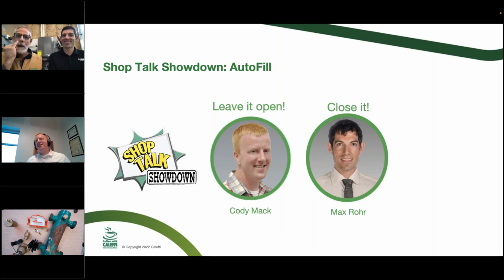No. See, so here's another thing to think about. Okay, say you close off that valve. Okay, you have a leak somewhere and you're not home. It's going to leak out a little bit. It's going to be all done, but then all of a sudden that pressure sensor in the boiler or the low water cutoff is going to take it offline, and then you're just going to freeze literally everything else in the entire house. So be prepared to buy all new toilets and all new piping and repipes, and it's going to be a nasty disaster of a mess.